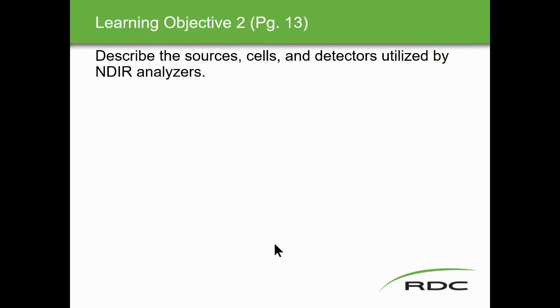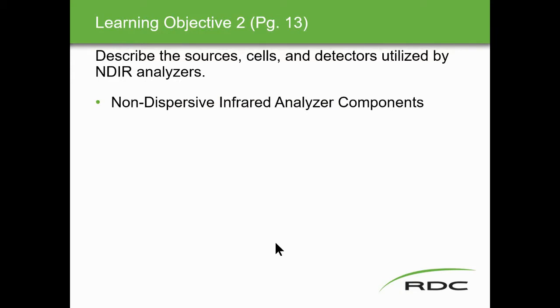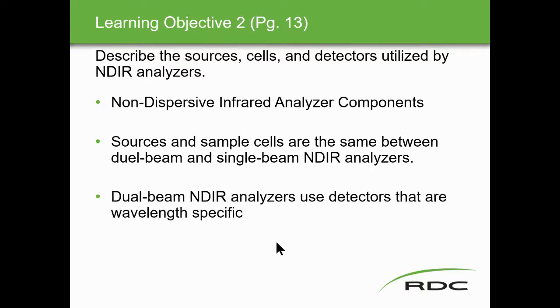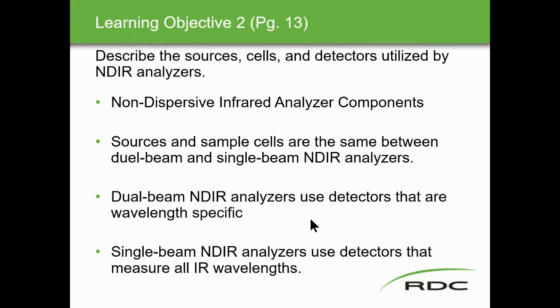Learning objective two: describe the sources, cells, and detectors utilized by NDIR analyzers. Non-dispersed infrared analyzer components — sources and sample cells — are the same between dual beam and single beam NDIR analyzers. Dual beam NDIR analyzers use detectors that are wavelength specific. Single beam non-dispersed IR analyzers use detectors that measure all IR wavelengths.